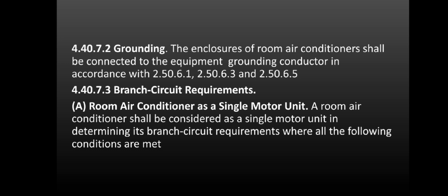If the AC is treated as a single motor unit, certain conditions must be met, such as the correct amperage in a single-phase connection. If the AC is the only load in the circuit, it must not exceed 80% of the branch circuit rating. If other loads share the circuit, like lights and outlets, the AC must not exceed 50% of the circuit rating. This ensures the circuit will not overload and trip.